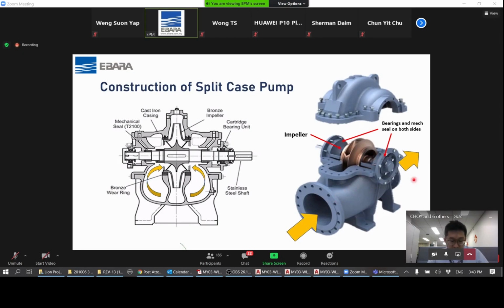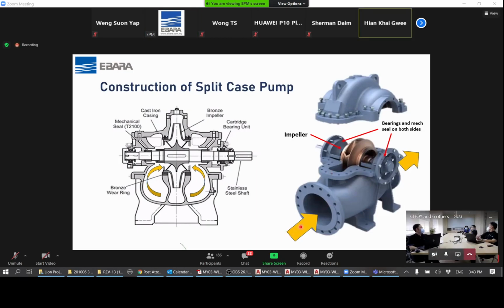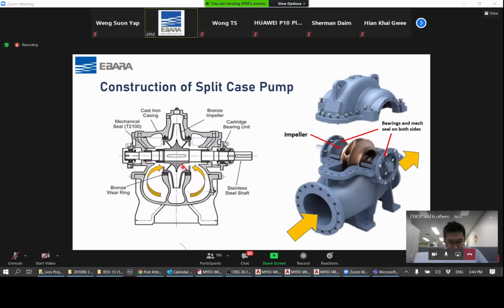Now, what do we mean by a double suction design? It simply means that the water, when it flows into the pump, is able to split into both sides of the impeller, because the impeller allows entry of water into both sides. And with that, as it rotates at its speed, it will generate the centrifugal force.